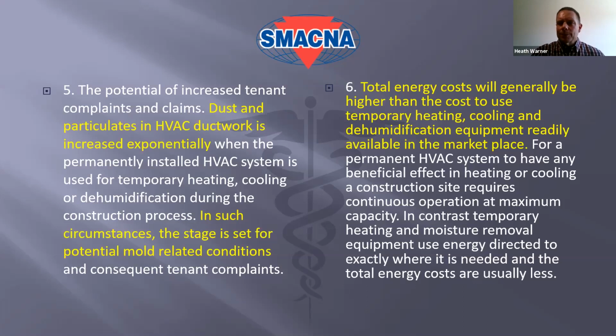The last one, and this one, more than any of the other ones, probably surprises most people. Total energy costs: to use the permanent system during construction, you're actually spending more money. Most contractors think that they're saving money by using the permanent system. And the reality is, the way the construction industry is, they might be if the owner is paying for fuel, but generally, because that HVAC system is designed to work under enclosed conditions, and because construction is open by nature, that system has to run full tilt 24/7 just to try to maintain the conditions of a tightly sealed and controlled building, meaning your costs are going to be through the roof.